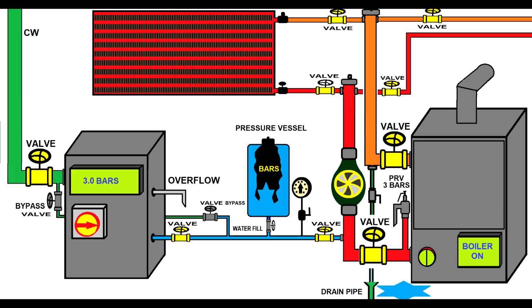The problem is at night when you turn off the unit, the heating agent will cool down, so the volume will shrink. Then the pressure will drop below the pressurization unit set point, and the pressurization unit will run the pump until the pressure reaches the minimum pressure which is set by you. In our case, I put 0.8, but it shouldn't necessarily be 0.8. It's up to what type of installation you have. So the pressurization unit will push, in this case, 0.8 bars.